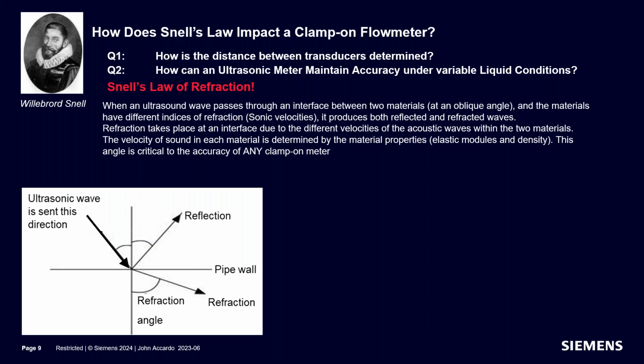So the effect of Snell's law occurs in two places. It occurs at the interface of the transducer and the pipe wall, and it also occurs at the interface of the pipe wall and the fluid stream, because again, that's another difference in density and sonic velocity. In this drawing on the left, you see a sonic wave being introduced to a pipe wall, represented by the horizontal line, and then there's a refraction where that sonic beam changes direction in the pipe wall. If we say above the horizontal line is the pipe wall and below it is the fluid, the same thing happens again. You have the sonic beam traveling in one direction in the pipe wall and changing direction in the flow stream.